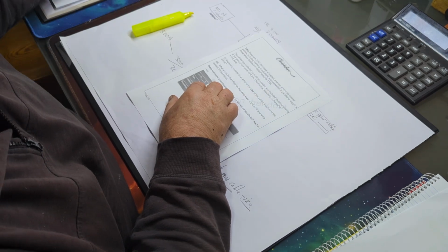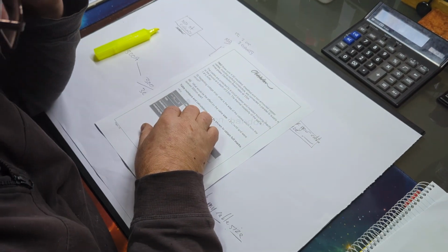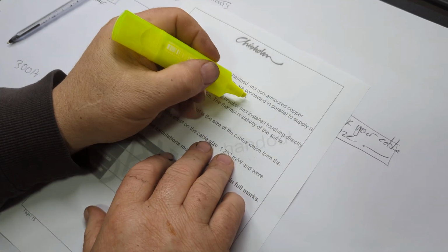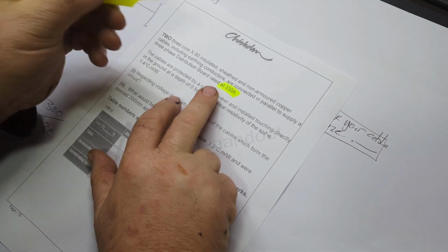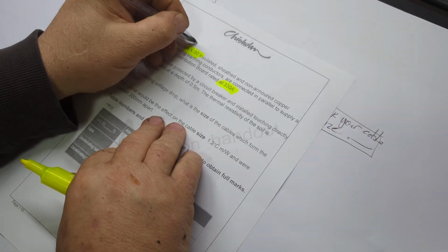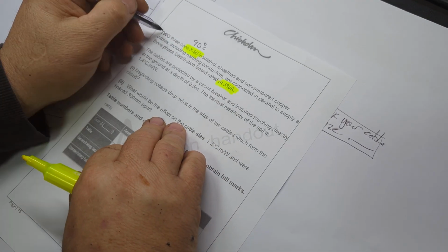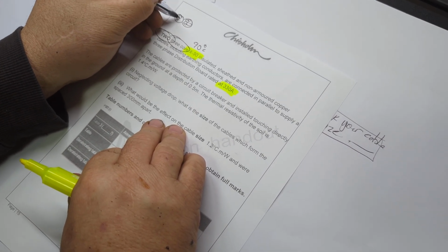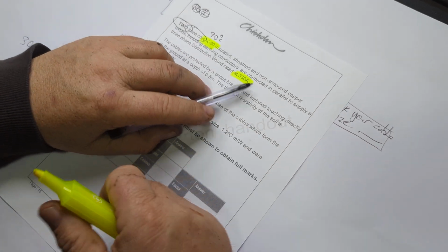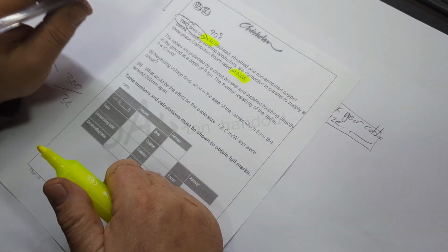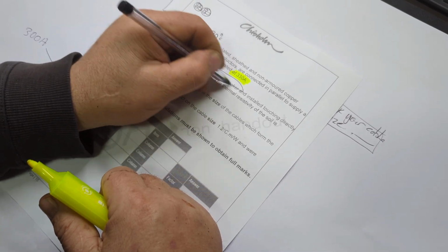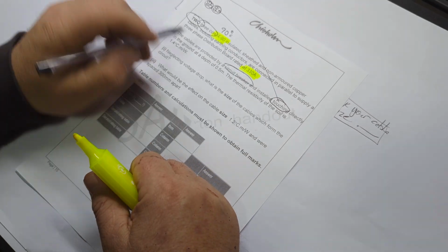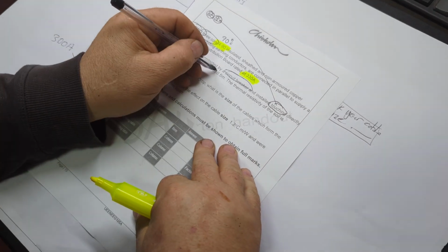Okay, in this video we're now doing a cable selection based on maximum demand. In this question, they've given us a maximum demand of 300 amps, X90 being 90 degrees. We have two 3-core cables connected in parallel. The cables are protected by a circuit breaker and installed touching, directly in the ground at a depth of 0.5.